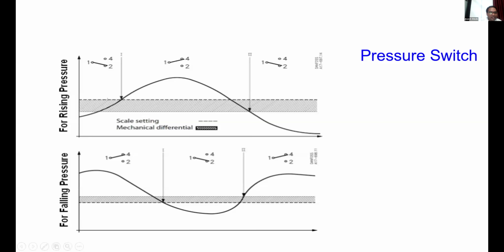Now see here, once this 30 bar is crossed, your contacts are changed from 2 to 4. It means it changed from normally closed to normally open. Again, once the set point is crossed here, the switch contacts are changed again. So in this way, the sensor works. I have taken just the example of pressure, but the working principle of all sensors is the same.